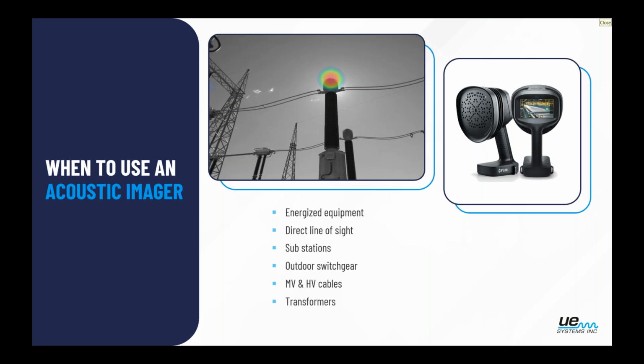Now, just like with any other device, there are places that we would want to use it and places that we would not. Once again, the point I'm making again, energized equipment, we do want to make sure that there's actually power running to this. Ideally, we want to have direct line of sight. So that would be things like substations, outdoor switchgear, energized yards, medium and high voltage cables, transformers outside. Once again, the bushing on top, the wiring running to it.